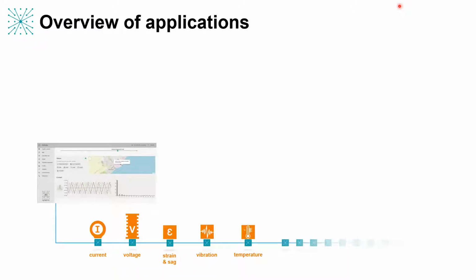Now, the first thing we can do with that, obviously, is publish it all on the process bus. For example, if you have relays in there, we are entirely compatible with the relays produced by the major OEMs. So if you just want to use this system as a super merging unit and get data into your systems cost effectively, for example, over wide areas for wide area protection, or for centralized protection around a substation, we can provide that data and it's entirely compliant with the standards.